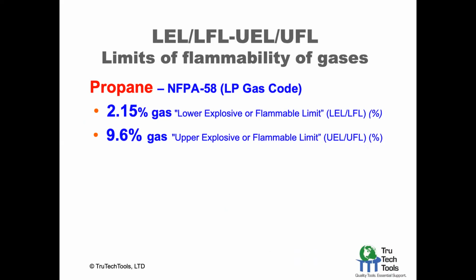So we'll go over again, two different gases, mainly two different combustible gases that you're going to encounter in residential situations: propane, which conforms with the National Fire Protection Association 58, the LP gas code. The lower explosive limit for propane is 2.15% gas. And that's probably the main one you have to remember, or at least be aware of. When you get to the upper explosive, we really don't want you folks working anywhere above the lower explosive. In fact, you're going to find out that BPI says it's only 10% of the lower explosive limit, and that's basically a no-go situation from there. They want you out. So it's a very safe use of this product, in that you'll be only at 10% of the LEL. But for information, the upper explosive limit is 9.6% gas.